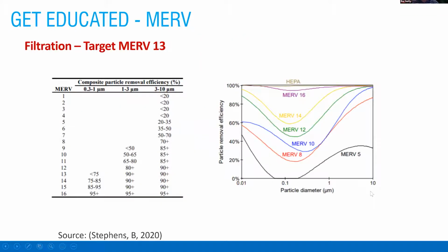All right, so filtration. This is already out there. Teachers unions have latched onto filtration as one of their first levels of protection. So where does the number MERV 13 come from? That is the recommendation from the task force for the filtration of particulate size. Remember that filters are dynamic, not static. So you get higher particulate efficiency with different particulates and with different filters. The graph on the right shows you between MERV 14 and 16, as the particles start to get smaller, you start to approach 80% filter efficiency.